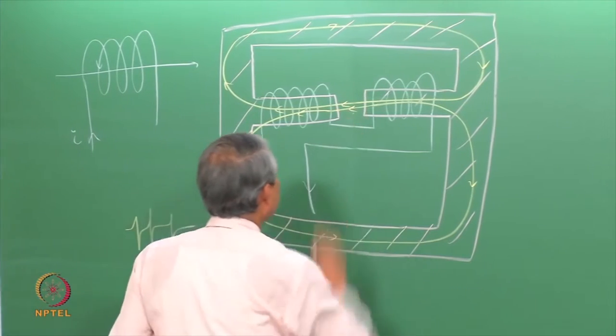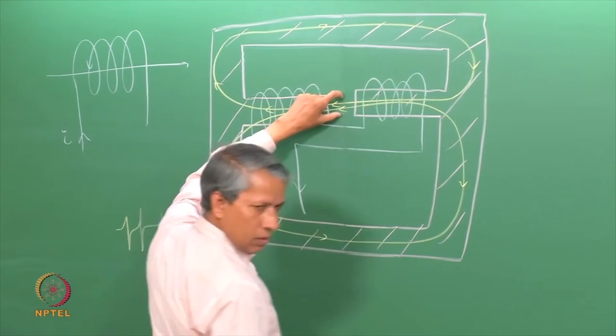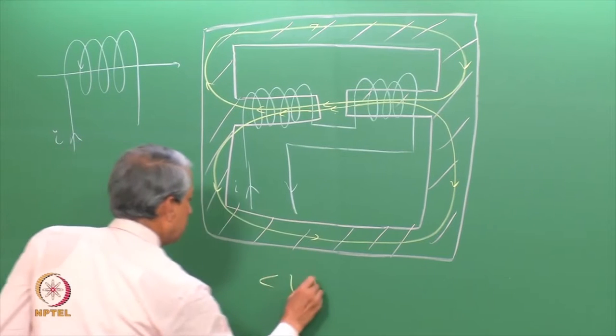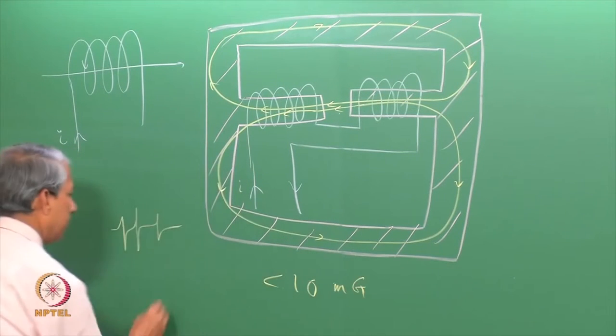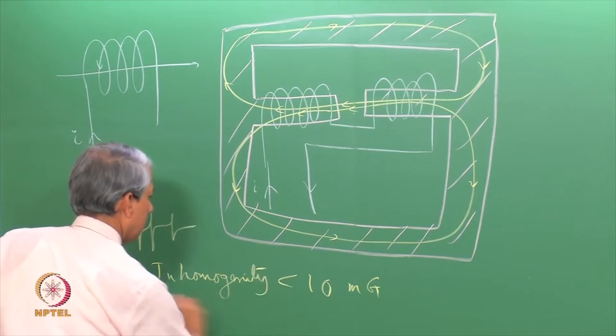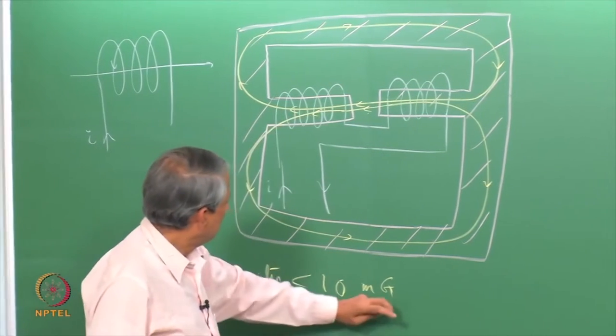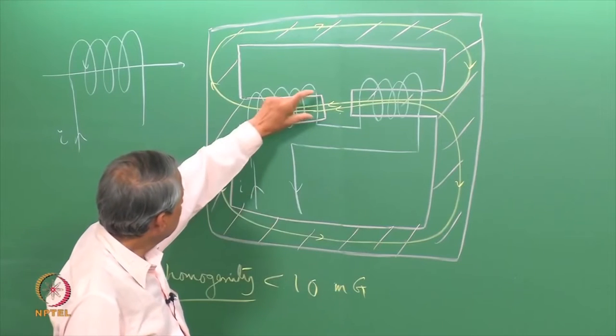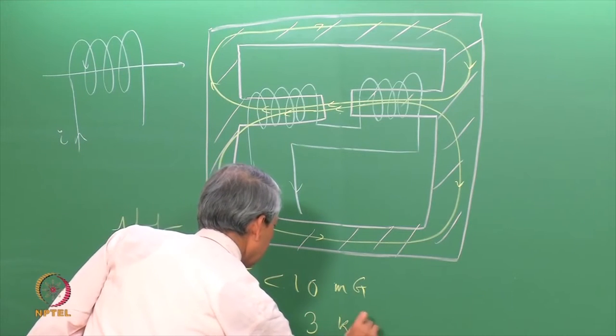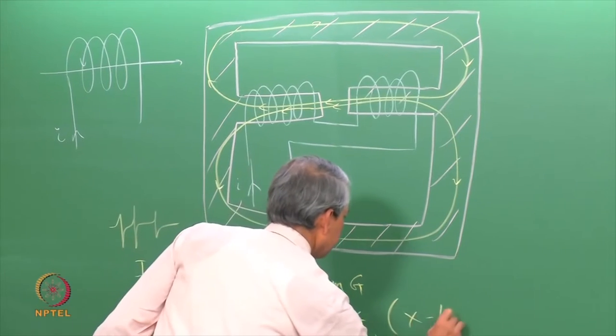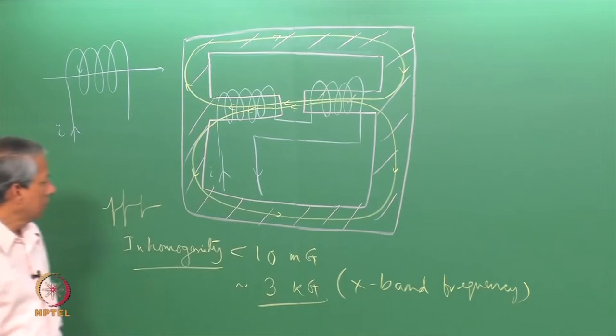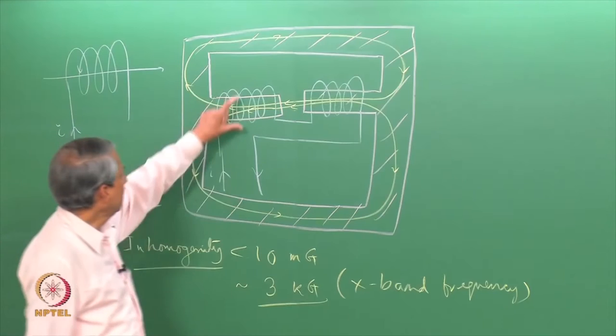A typical requirement is that this inhomogeneity within the sample, within the cavity dimension, the inhomogeneity should be less than 10 milligauss. This is the inhomogeneity necessary in the presence of a magnetic field which is of the order of 3 kilogauss which is our X band frequency, which is the typical requirement of the homogeneity of the magnetic field.